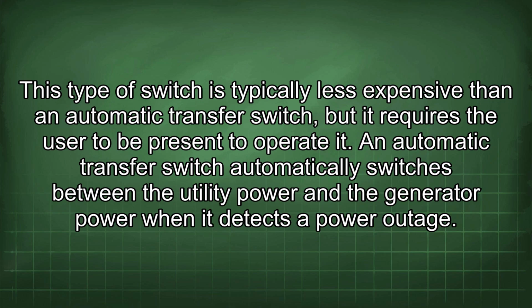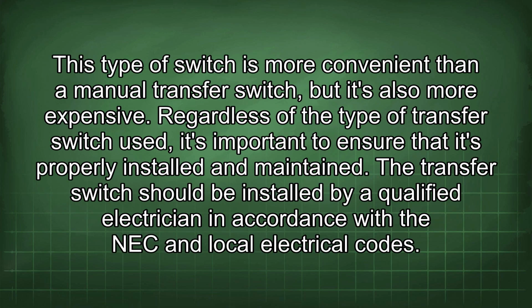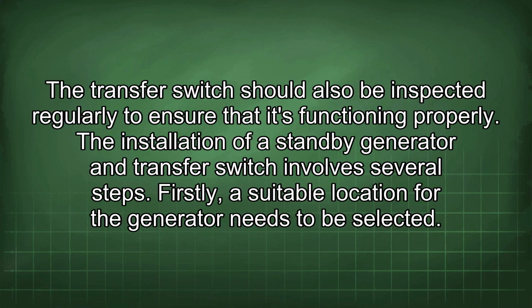An automatic transfer switch automatically switches between the utility power and the generator power when it detects a power outage. This type of switch is more convenient than a manual transfer switch, but it's also more expensive. Regardless of the type of transfer switch used, it's important to ensure that it's properly installed and maintained. The transfer switch should be installed by a qualified electrician in accordance with the NEC and local electrical codes. The transfer switch should also be inspected regularly to ensure that it's functioning properly.